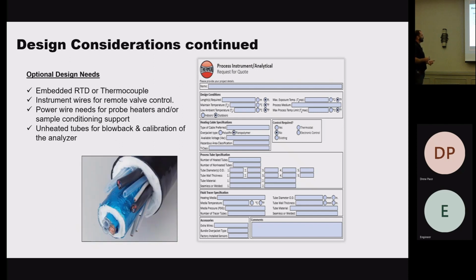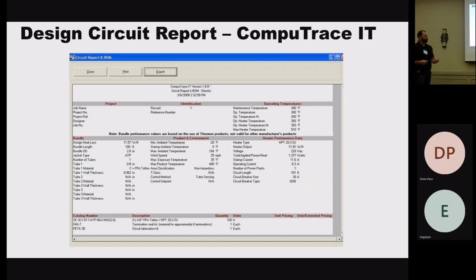Other things to consider: the sensors, alarm wires, power wires, whatever else you need, blowback, calibration tubing. Once we get all that information, what's unique about Thermon is that we have our own software with all the information from our heater cables that we've developed from R&D over the years. We put all that information in, and it spits out this report. What's neat about the report is that it shows a lot of information about your heater cable, whereas you may be maintaining 300F at -20.